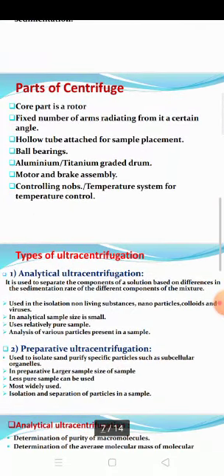The parts of a centrifuge can be divided into seven major parts. The core part is the rotor, with a fixed number of arms radiating from it at a certain angle, and hollow tubes attached for sample placement. Then there are ball bearings, an aluminum titanium graded drum, motor and brake assembly, controlling knobs, and a temperature system for temperature control.